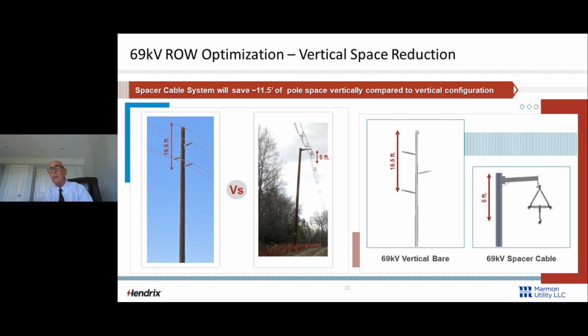Now, the first job we did at OPPD, we wrote an IEEE paper with the OPPD engineers and discovered that we were reducing the pole heights not by 5 feet, but by 21 feet. That's a heck of a lot of vertical reduction. So the answer is, yeah, it's going to depend on what you are comparing. You've got horizontal, you've got vertical construction, what kind of poles you're using, where are your insulators, what kind of clearance you need, are you going over railroads, et cetera. But in this case, we saved 16.5 feet.